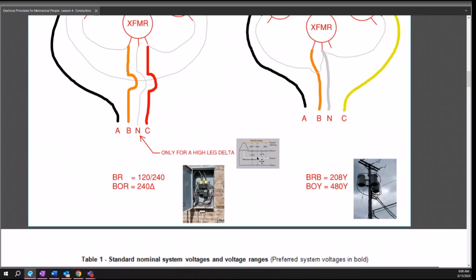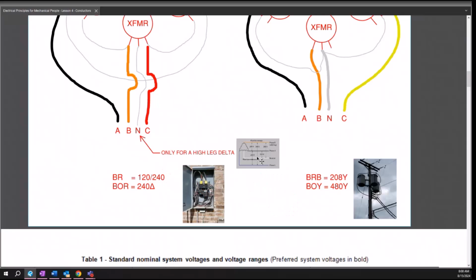Now, the fun part about this is up until 1984, I think, somewhere around there, either late 70s, early 80s, the convention, the unspoken rule, was the high leg goes on the C phase. So I've come across it where it is an actual high leg delta and the orange is on C phase. And when we did work out there, we had to annotate, hey, the high leg C phase, be wary, be careful, don't connect anything like that. And we had to reflect that in the panel schedule as well. But most of what you may be working on, it should technically be on B phase. Don't move it. If you find it on C, just leave it as is and annotate it. But nowadays, it is a requirement for it to be on B.